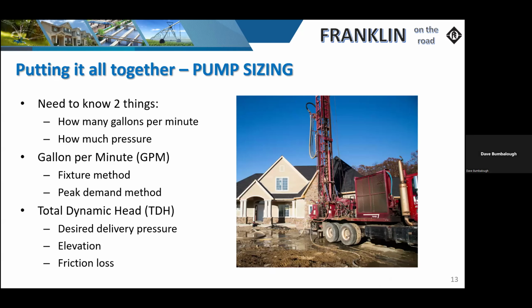So as we look at sizing a pump, there are basically two things that we need, especially when it comes to sizing a submersible. Oftentimes, as the well is drilled, the installer or the driller does not want to over-pump, but that's not the correct way of sizing a system. The proper way is to size it for the application, not what the well produces. There are other things that we can do if the well is not a good producing well, and I'll cover those in just a second. So the two things that we need are basically the gallons per minute for the application.